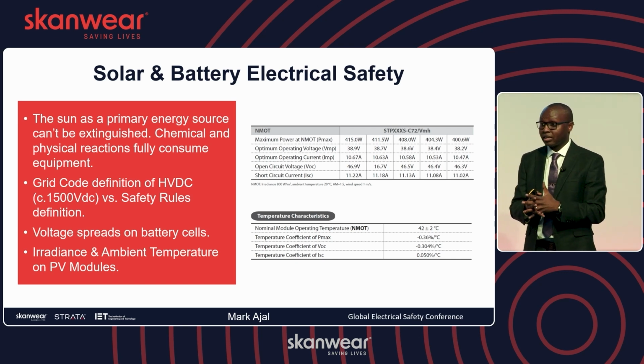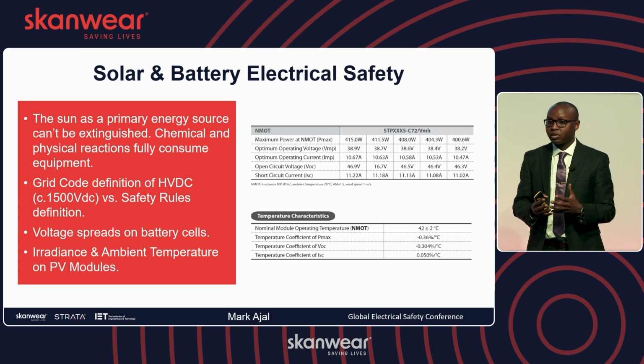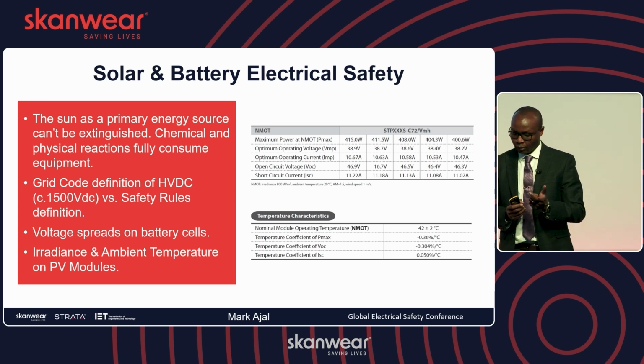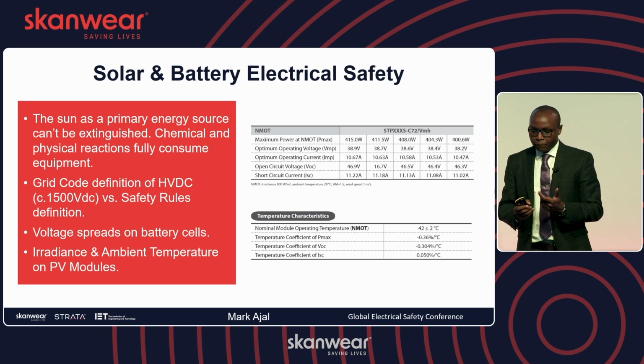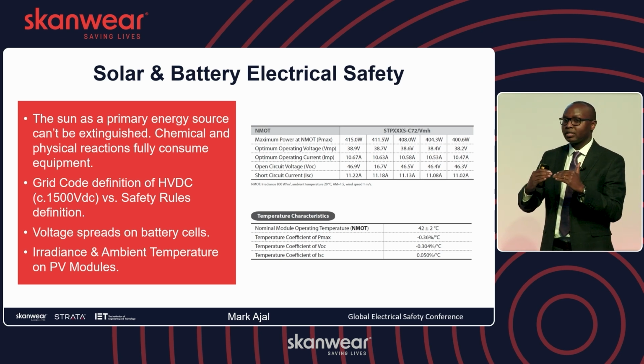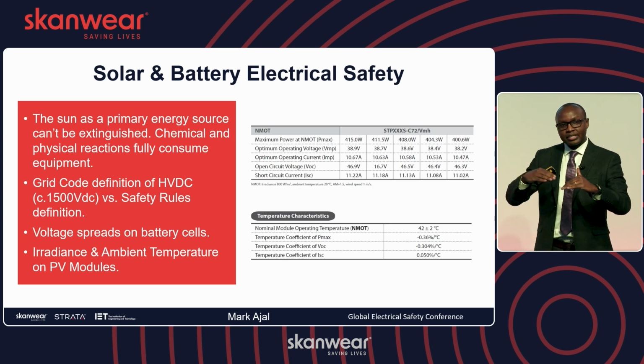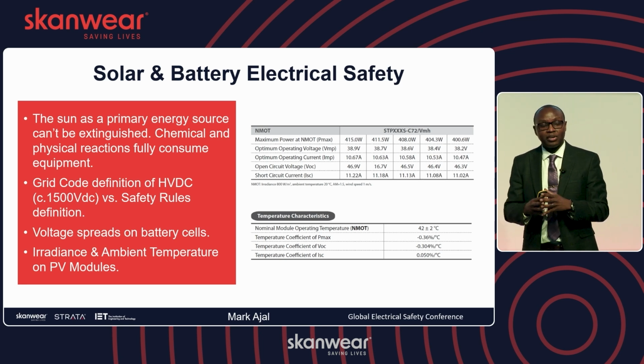Do your grid codes capture that in the jurisdictions you work in? Do the safety rules for the organizations you work for capture those nuances if you're having any DC systems? Then within a battery facility or within a solar PV facility, because of irradiance hitting different panels at different points, or simply because of the way the batteries are wired, you try and wire them in a sequential string, where the voltages are additive. It's a numerical addition. One string plus the other gives us the total voltage of the bank or of the PV array. There'll be a delta. You'll not have a consistent voltage. So those voltage spreads mean if there's a voltage difference, current is flowing.